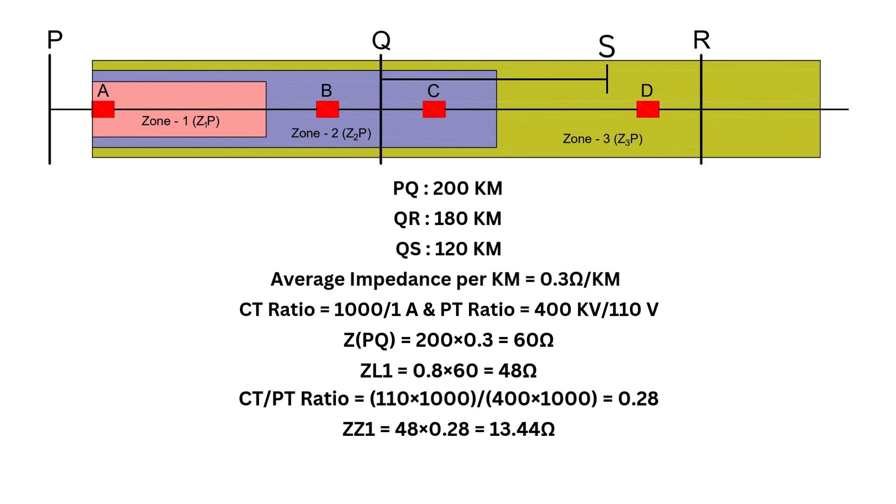So, the zone 1 setting for relay A will be 13.44 ohms. If the relay senses an impedance less than this, it will trip the breaker. The time setting for zone 1 is instantaneous because we want to isolate the fault immediately. Now you might wonder, why don't we set zone 1 to 100% of the line length?